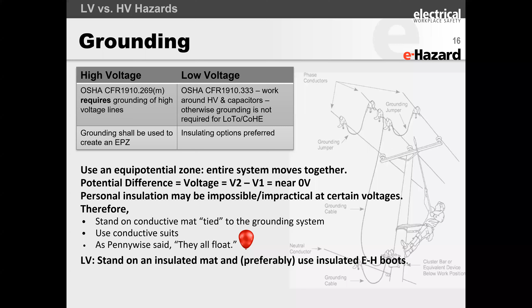At low voltage, we don't want to ground for an equipotential zone, but what we want to do is cover up the equipment. If we cannot cover up the equipment, we want to use gloves. We want to use insulated shoes. We want to use electrical rated hard hats. We want to use rubber insulating gloves. I think I said rubber insulating gloves twice. Well, maybe because it's so important.